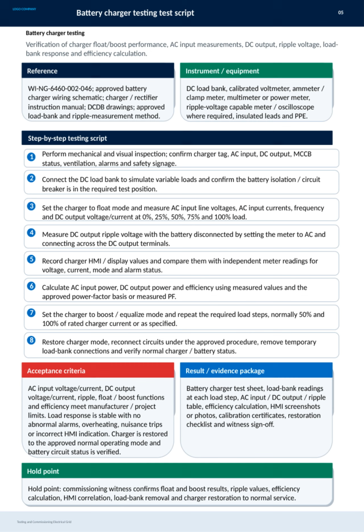First, we begin with a thorough mechanical and visual inspection, ensuring all charger tags, AC input, DC output, MCCB status, ventilation, alarms, and safety signage are in proper condition. Then, we connect the DC load bank to simulate variable loads and verify that the battery isolation and circuit breakers are in the correct test positions.